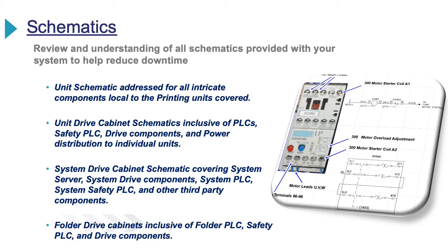We will be covering the printing units, the system, unit, and folder drive cabinet schematics in detail. We will also address the hardware safety loop going through the press and going out to the redundant PLCs. Some of the material is not displayed on the schematics and must be extracted from the assembly drawings. The schematic and assembly drawings may need to be reviewed together.